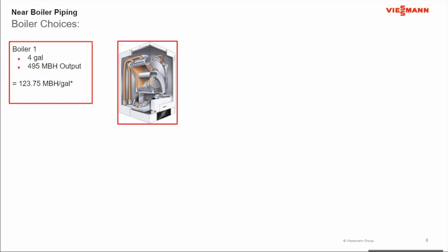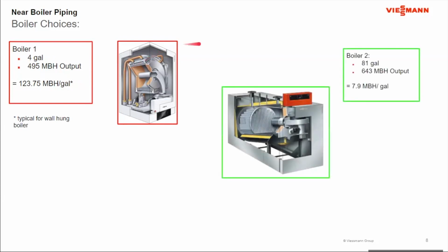Now, if you look at that number, we start to compare it to the floor standing boiler. A little note about this number is that this amount of BTUs per gallon within the boiler is fairly consistent for what you see for a wall-hung water tube boiler. But really, that's the amount of energy based on the amount of gallons in the boiler itself. Now, if I look at the floor standing boiler, it has 81 gallons of water and its output is 643,000 BTUs. I do my math, I'm at 7,900 BTUs per gallon of water. Significantly lower ratio of water to firing rate of the boiler.